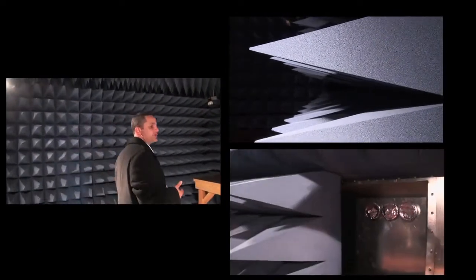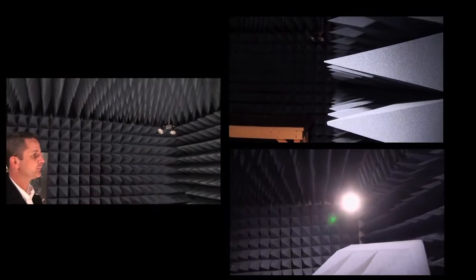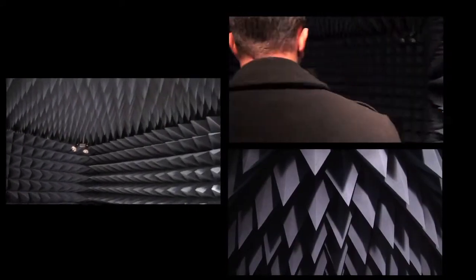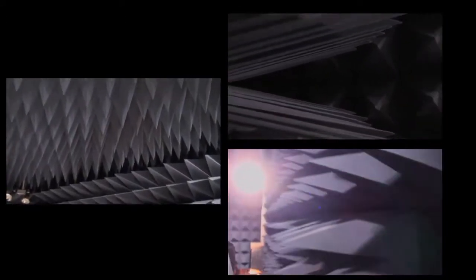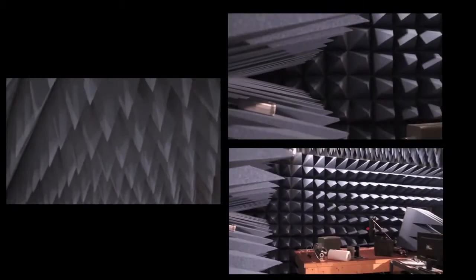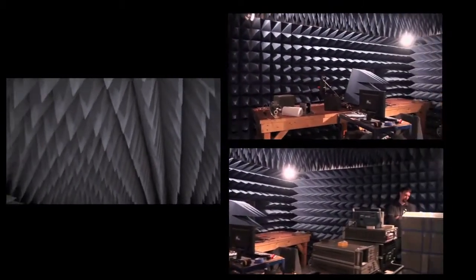So this is inside one of our MIL chambers. As you can see, the chamber's lined with 24-inch pyramidal anechoic material, used for absorption of electromagnetic waves per MIL-STD-461 as well as DO-160.